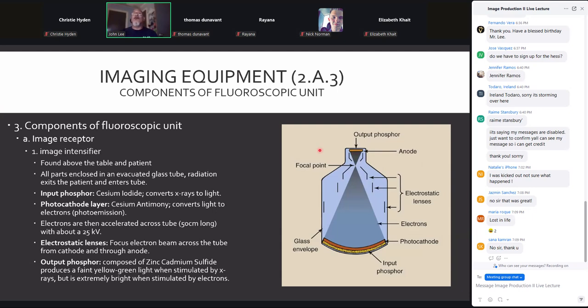Now, when we turn on a fluoro system, there is going to be 25,000 volts, or 25 kV, while that system is on. That's the potential difference between the cathode end and the anode end. So those electrons are being moved across to that output phosphor by that potential difference. Okay, the only difference is we're going to produce light at the other end. We're not going to produce X-rays with those electrons. Now, the output phosphor is zinc cadmium sulfide.